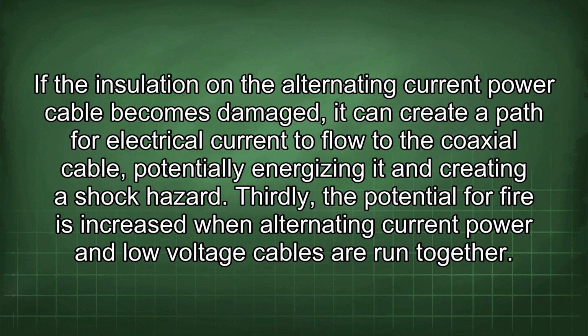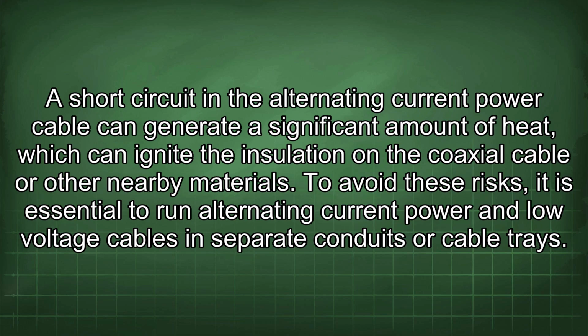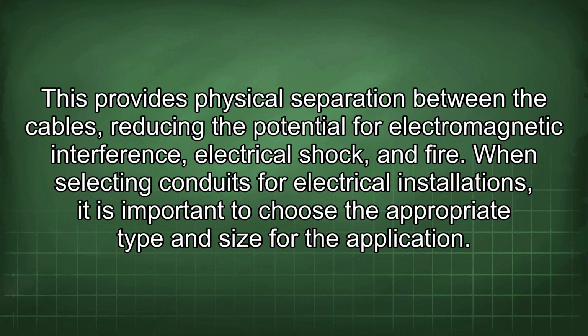Thirdly, the potential for fire is increased when alternating current power and low voltage cables are run together. A short circuit in the alternating current power cable can generate a significant amount of heat, which can ignite the insulation on the coaxial cable or other nearby materials. To avoid these risks, it is essential to run alternating current power and low voltage cables in separate conduits or cable trays. This provides physical separation between the cables, reducing the potential for electromagnetic interference, electrical shock, and fire.